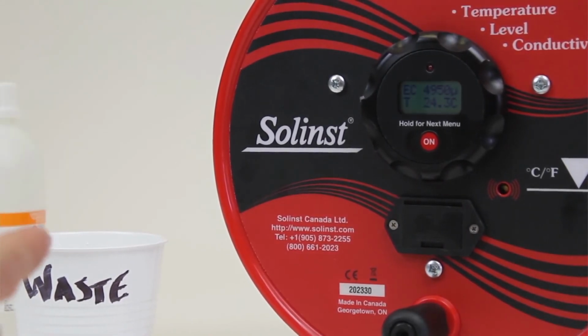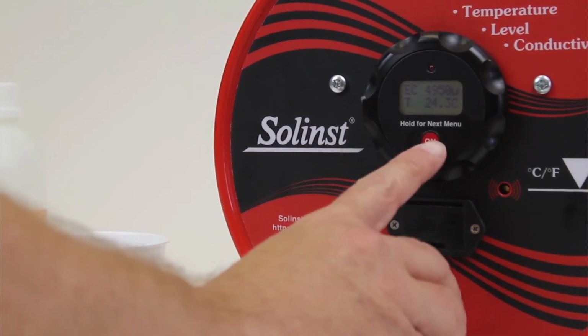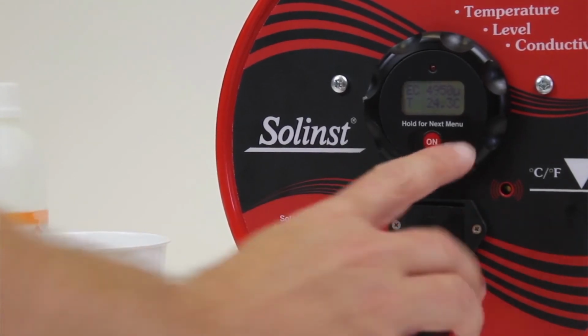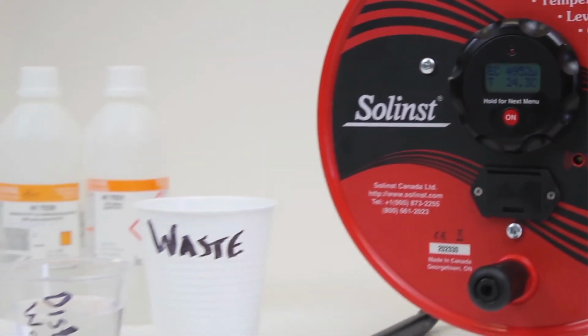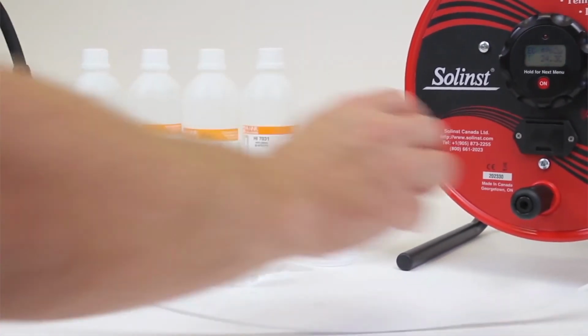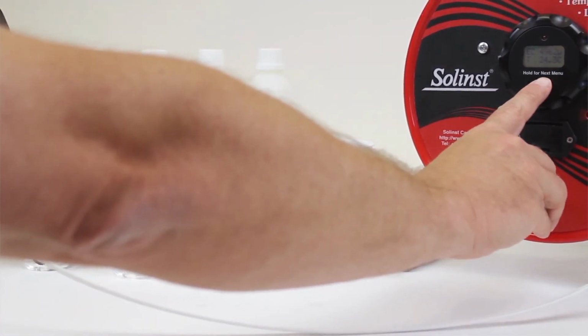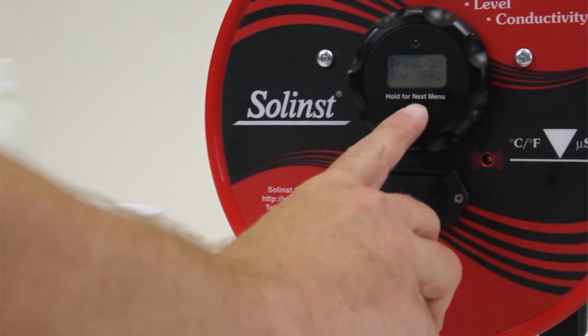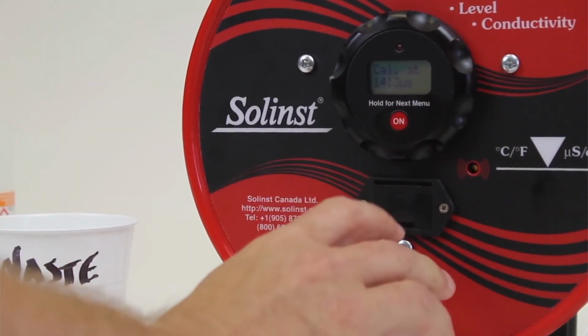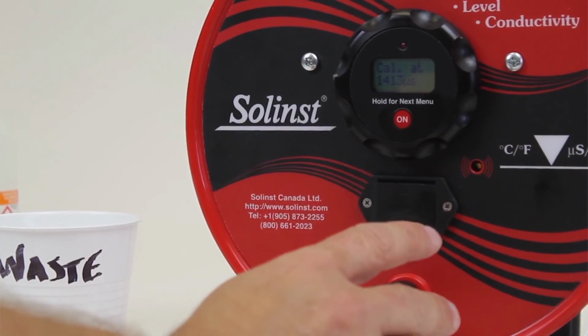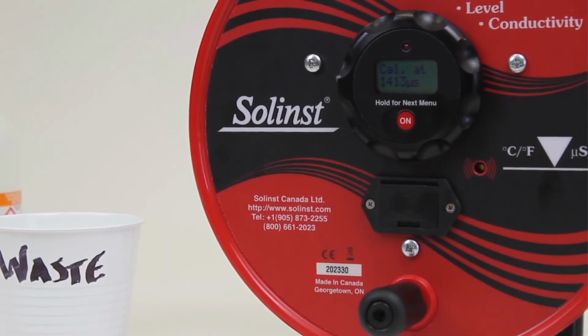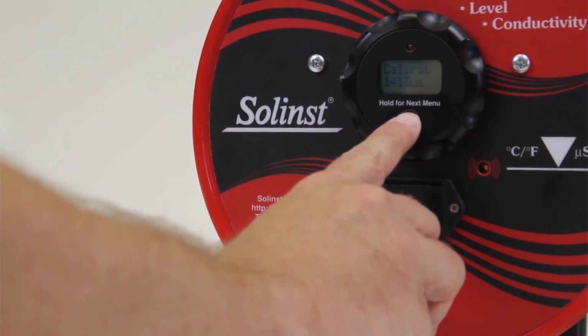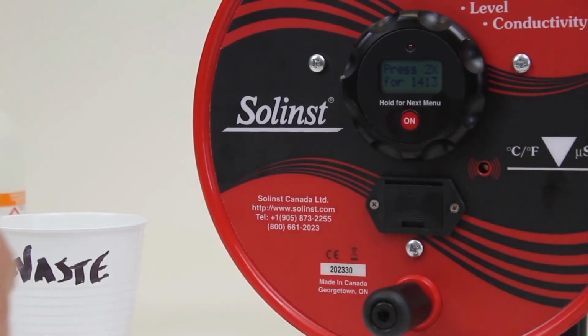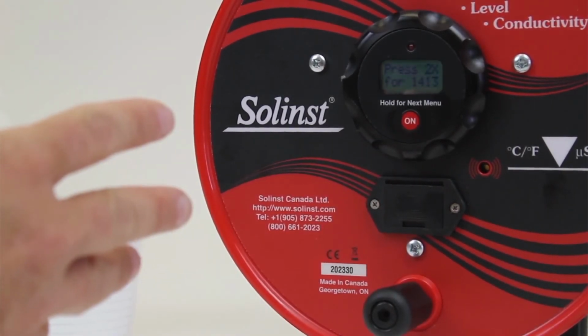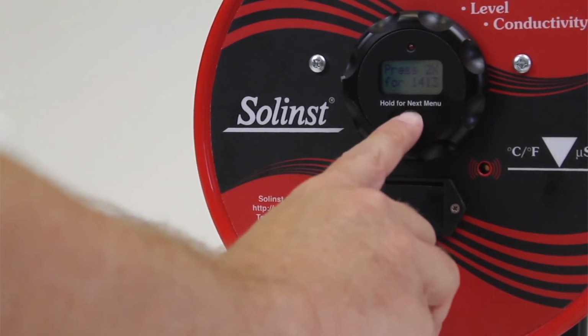So again, to go to my next menu so I can look for the 5000 calibration step, I'm holding the probe off the bottom of the cylinder where I have my solution. I'll press and hold to bring to my next screen. I don't want to turn it off, so I'm going to press and hold again. It says cal at 1413. I don't want to do that. This time I'm in 5000 solution, so I'm going to press and hold again. I'm not doing the calibration at 1413, so I'm going to press and hold.